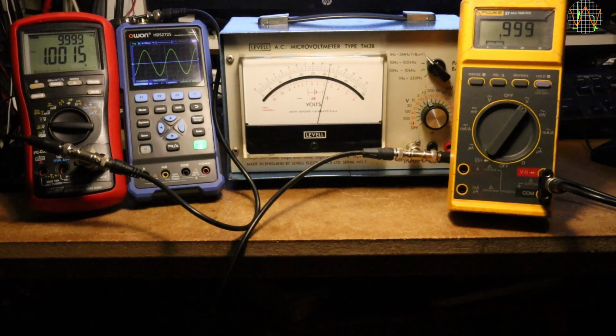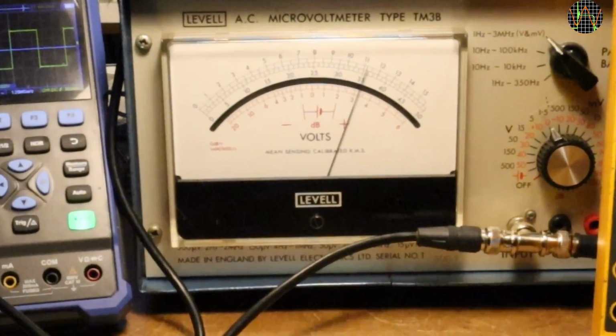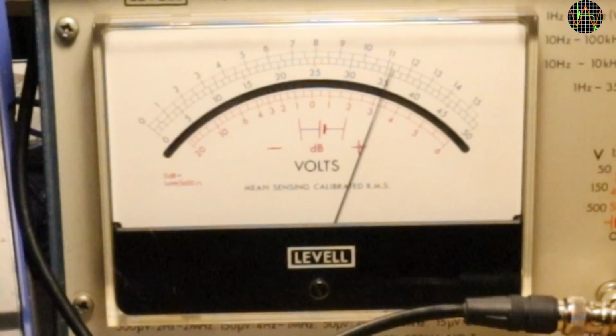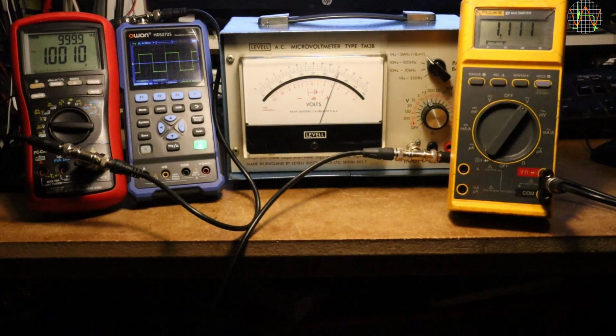It is easy to reveal this trick by switching to a square wave of 50% duty cycle and 2 volts peak-to-peak value. In this case, the true RMS value is equal to the average and mathematically exactly half the peak-to-peak value, or 1 volt. This is shown correctly by true RMS meters as the red multimeter on the left, but the TM3B and the Fluke 27 internally also get 1 volt average, but then mistakenly apply the 1.11 factor and therefore show 1.11 instead. For more on this, I provide a link to a couple of videos explaining true RMS. For other waveforms, or indeed mixtures of waveforms, the average and RMS values can be quite different, which is something to keep in mind when using non-RMS meters like the TM3B. They are really made for nice sine wave inputs.